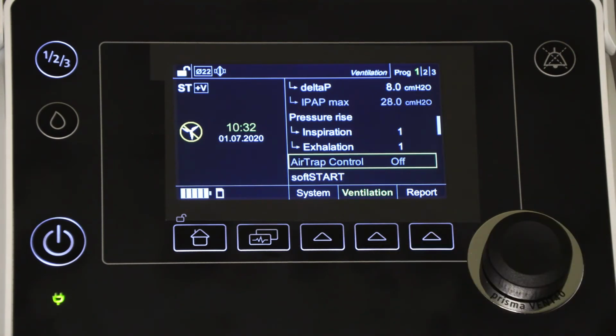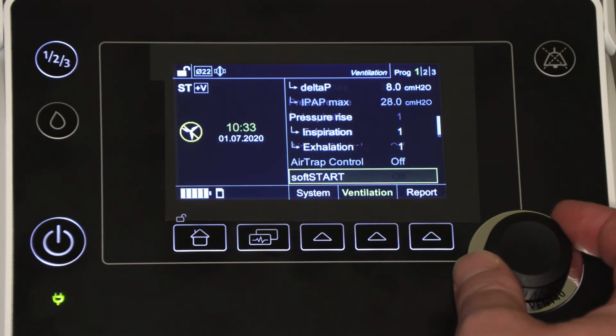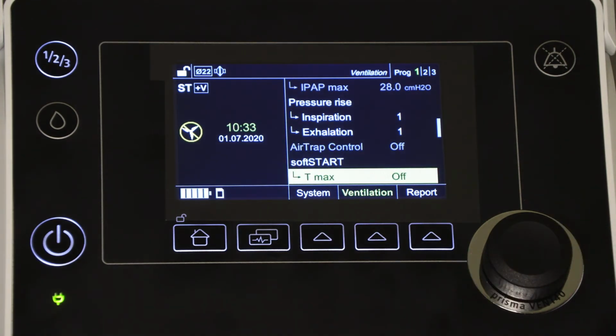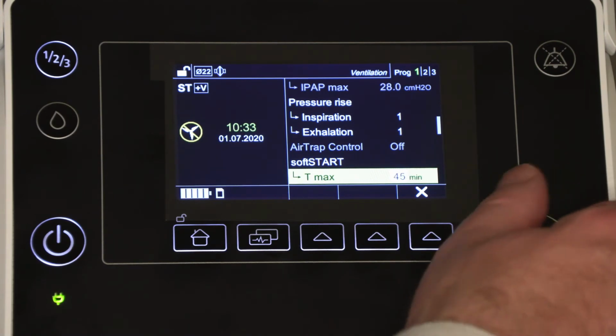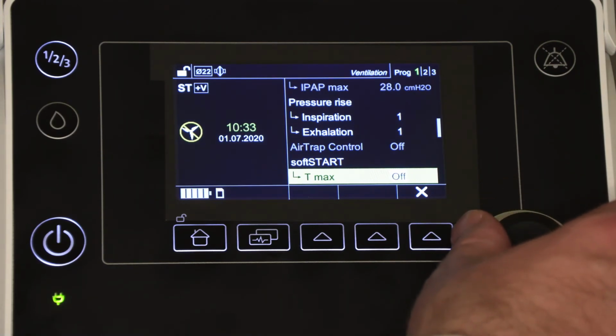The air trap control setting, when turned on, enables prismaVENT to optimize the expiration time to avoid air trapping and intrinsic PEEP. This feature is useful for COPD patients. It can't be turned on if the volume compensation feature is activated, and if it's not required, it can just be left off. The soft start feature is otherwise known as ramp, which can be set to a time of anything between 5 to 45 minutes if required.